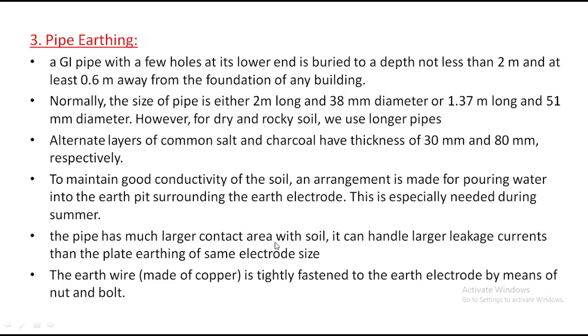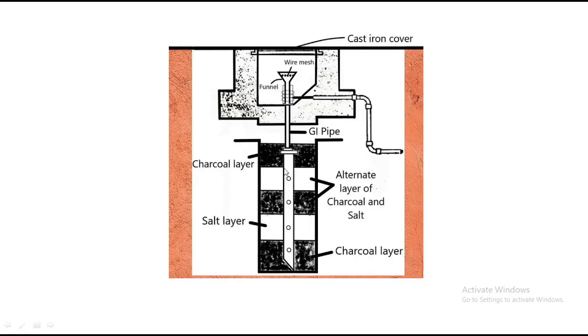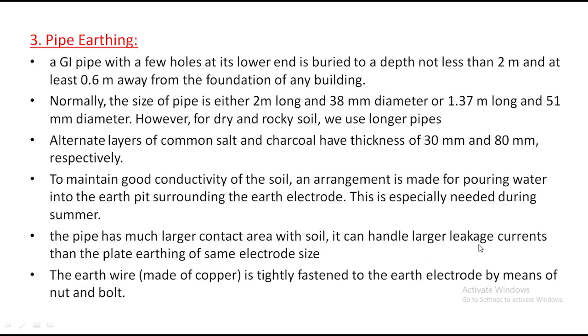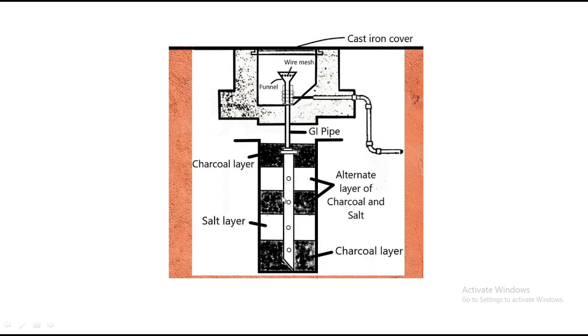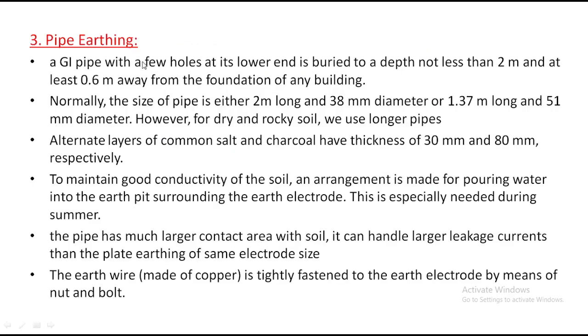This pipe has a much larger contact area with soil. Generally the pipe here, look here, has more contact area compared with the rod. It can handle larger leakage currents than plate earthing of the same electrode size. We are not discussing plate earthing now, but compared with plate earthing, this handles very large leakage currents. Next, the earth wire made of copper is tightly fastened to the earth electrode by means of a nut and bolt. We have the earth electrode there and we connect to it. Understand? This is about pipe earthing.